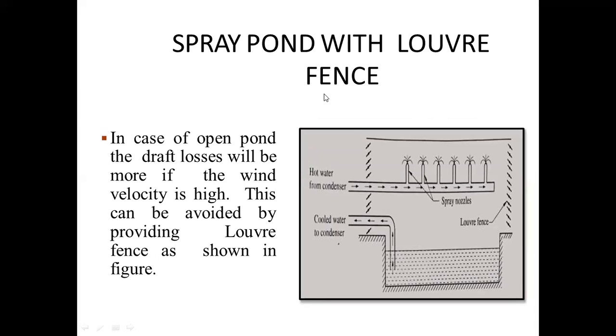Now, spray pond with louvre fence. See, there are nozzles, and here we are using, you can see we are using louvers so that evaporation loss can be minimized. In case of open pond, the draft loss will be more if wind velocity is high. This can be avoided by providing louvre fence as shown in figure.